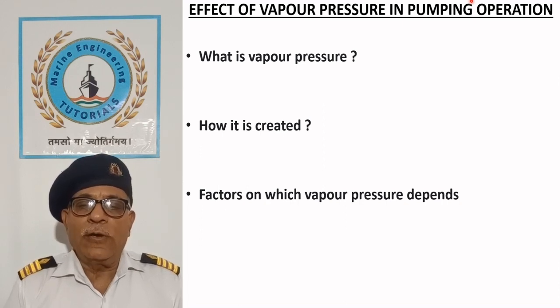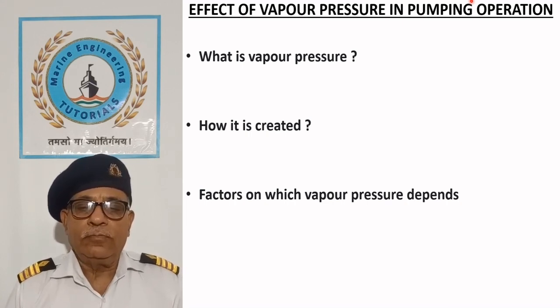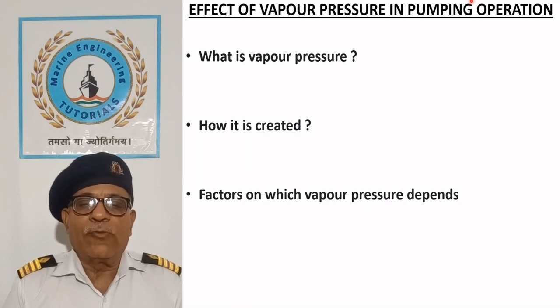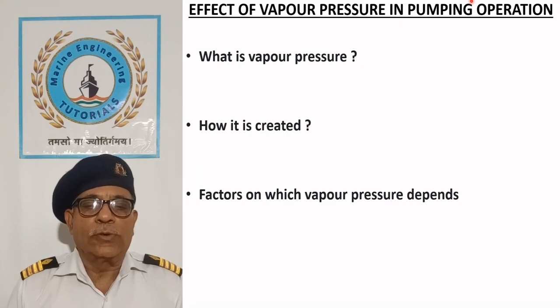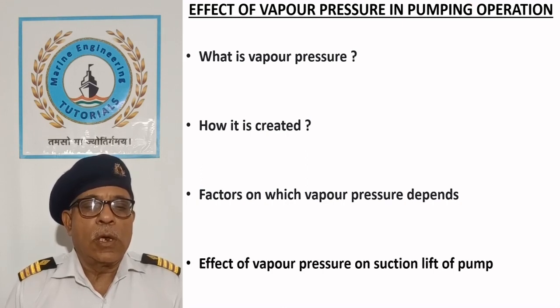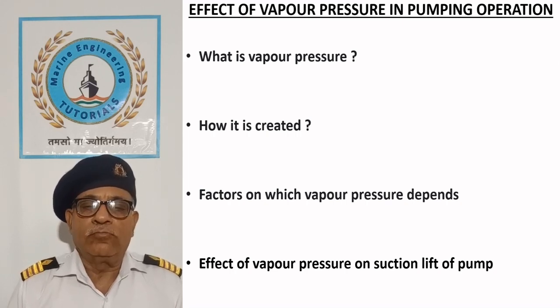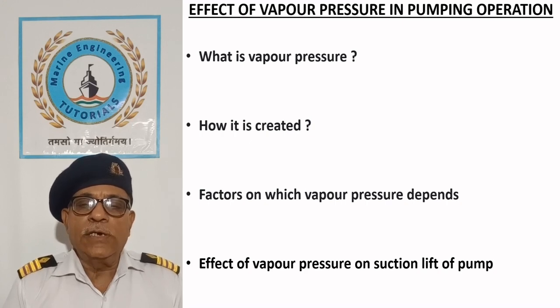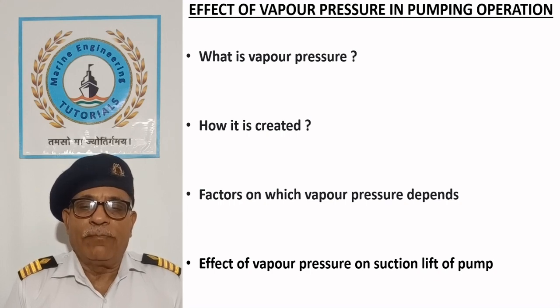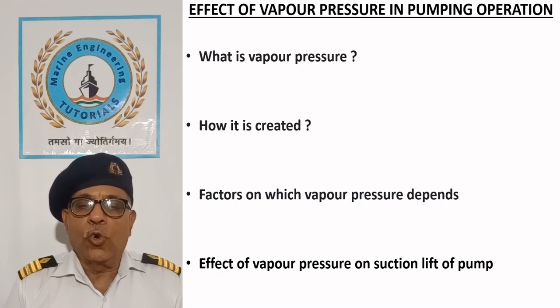Flammable liquids with flash point below 60°C give off more vapors and have high vapor pressure, in comparison with non-volatile liquids having flash point above 60°C and low vapor pressure. Vapor pressure of a liquid increases with increase in temperature due to increase in the kinetic energy of molecules. Increasing vapor pressure lowers the suction lift of the pump. Although water has low vapor pressure, it increases with rise in temperature and can affect pumping adversely, as shown in the next slide.